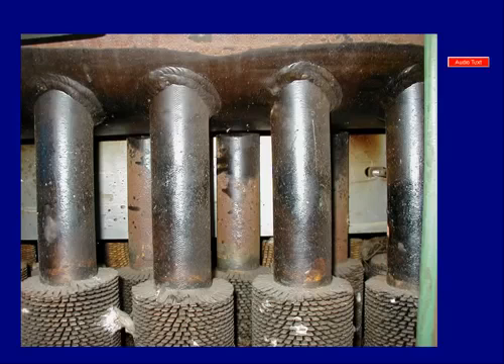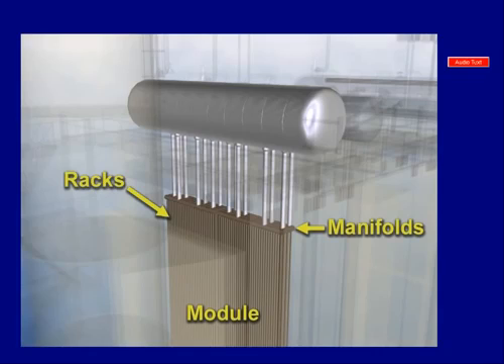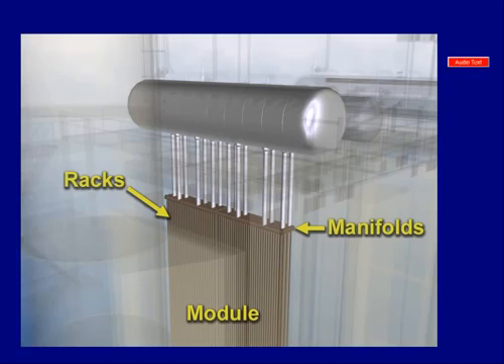The HRSG is primarily composed of finned tubes. The outer side of the HRSG tubes are covered with fins. These fins are designed to enlarge the tube's surface area to increase the rate of heat transfer. Boiler racks are rows of finned tubes that are welded to distribution and collection manifolds. Boiler modules are composed of racks which are arranged together. The inflow-to-outflow on a pipe rack can be from the top header to the bottom header, or from the bottom header to the top header. The headers of adjacent boiler racks are placed against each other in order to avoid bypass flow of exhaust gases outside the modules.